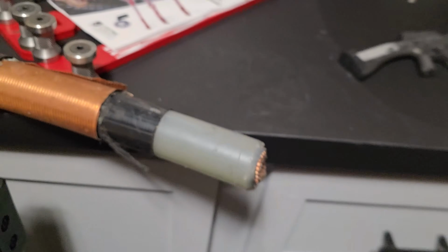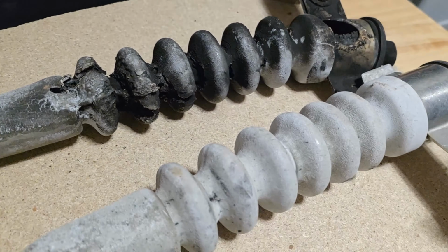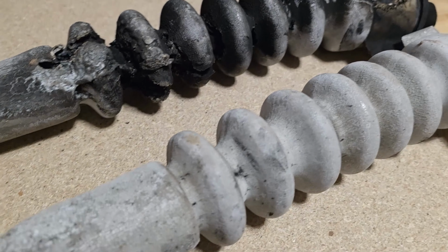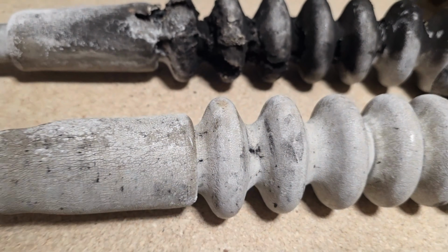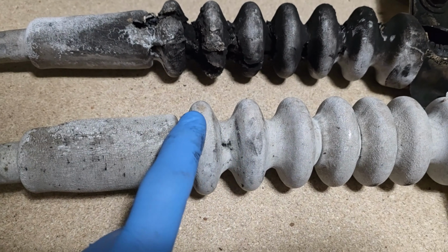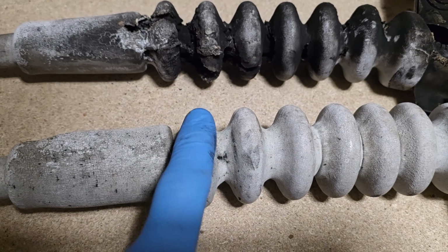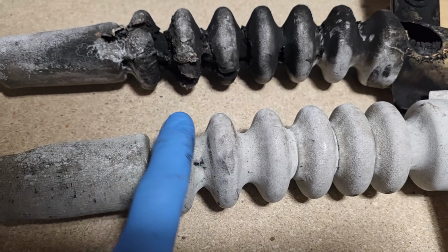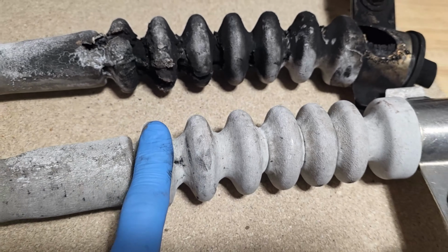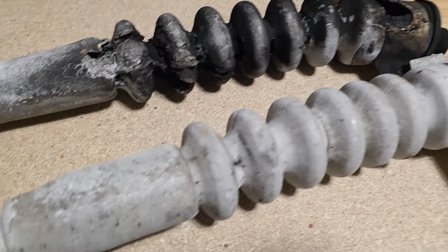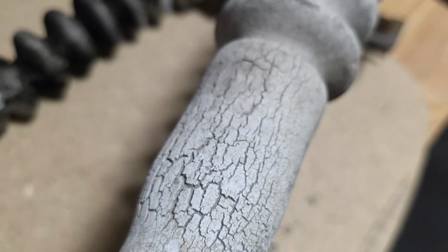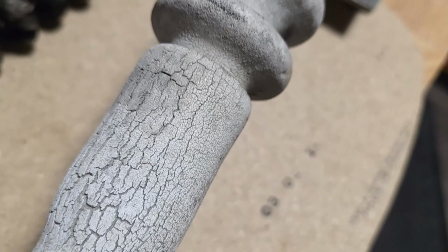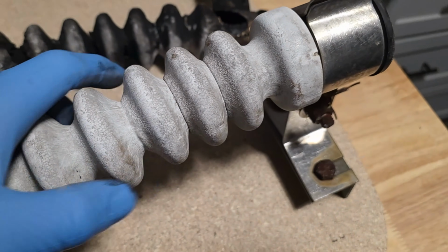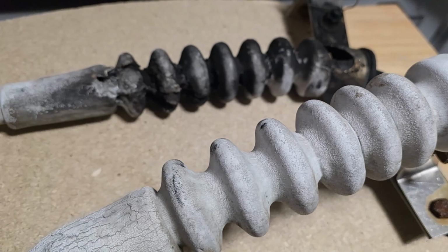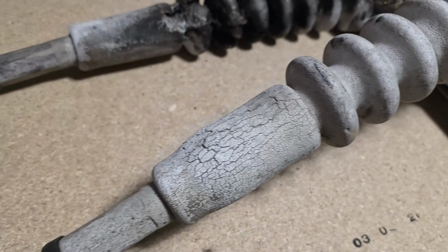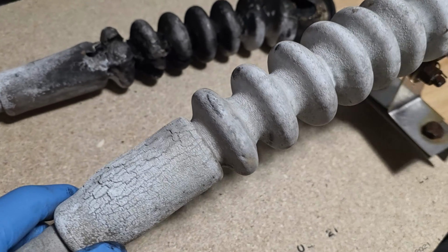That's the same with our insulators, except for this guy. So technically speaking, and definitely don't ever do this, but there's 7,200 volts in there. There's enough insulation value right here for it not to go through that to my finger. But these being out in open air, and this is a great example, over time they get really bad UV damage. You get salt spray, could be from natural salt spray from being close to a body of water, could be from the roads. You also get mineral deposits in the rain.